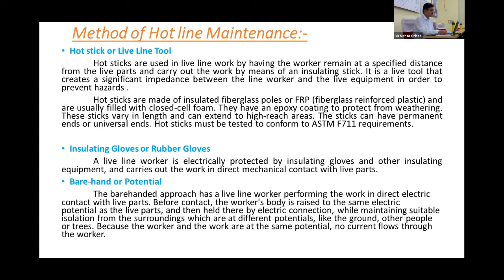Some advanced things we may not have at state level. I understand the power grid has helicopter-based live line maintenance also. A lineman wearing a Faraday suit can work on a live line while being transported to the lines by helicopter. The worker performs maintenance sitting on an outer ring platform attached to the helicopter, which hovers next to the line, saving a lot of time for long distance 400 kV lines passing through forest, where reaching each location otherwise takes a lot of time.